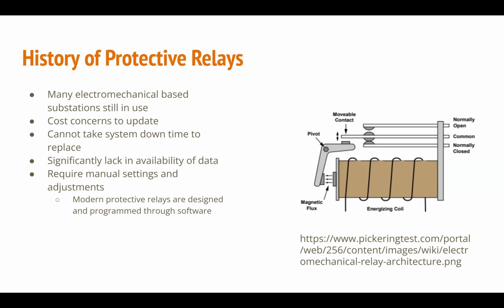That's another problem with these electromechanical relays: you would put in the prints to say all the set points of these electromechanical relays need to be this exact number, and then a person actually needs to go out and set those correctly and test them. Where with a newer microprocessor-based relay, you have software where you design everything and then load in the settings, and you know what's in that relay is exactly what you designed. There isn't that human error factor.